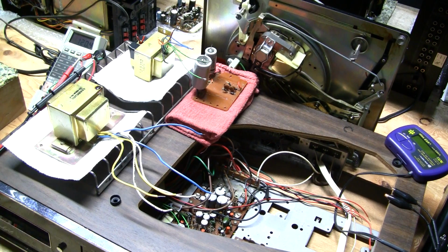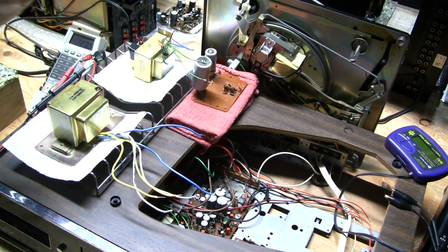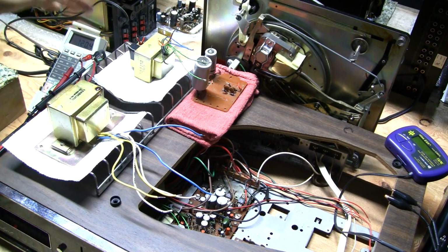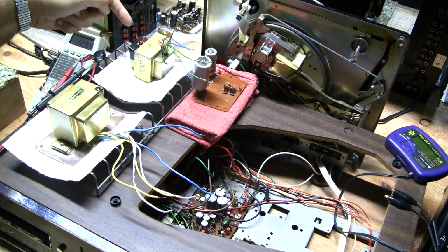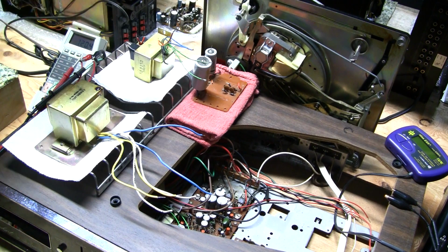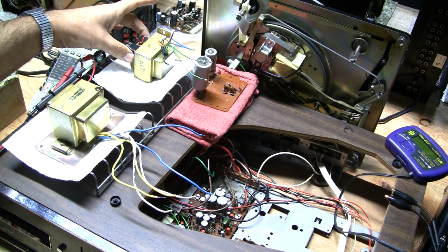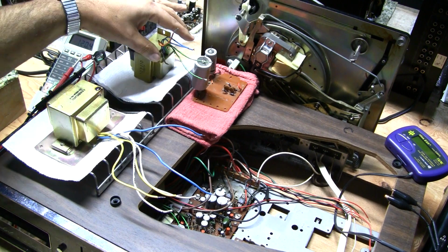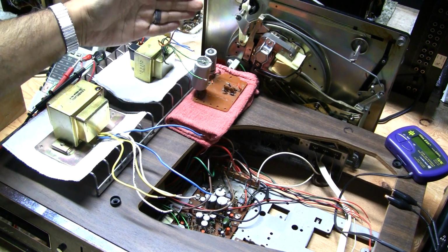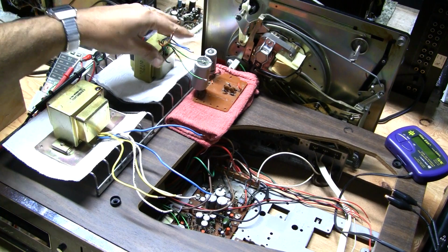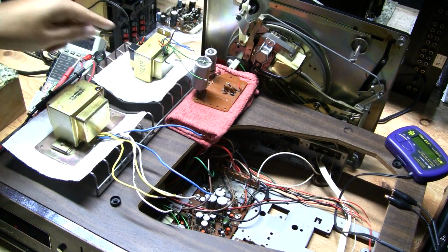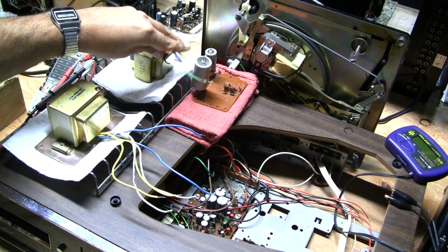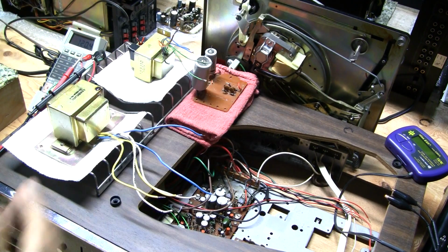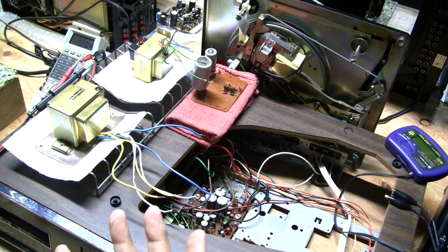So in quick review, what we have going on here is a bad transformer. We fed 120 volts from the wall into the primary side of our transformer, and we should have had different voltages available on the secondary side, but we did not. Now, I could have got to that conclusion a little quicker without having to lift the transformer out and all that, but that's okay.